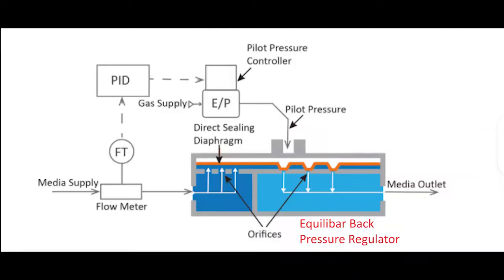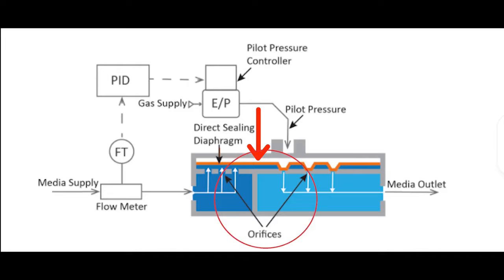The Equilibar back pressure regulator is used to control pressure upstream of the device by using a 1-to-1 pneumatically loaded set point on the dome of the regulator. A direct sealing diaphragm in the dome of the unit covers a field of orifices and adjusts its position to allow flow through the orifices to maintain a desired pressure set point. Using this relation, we can additionally control flow.